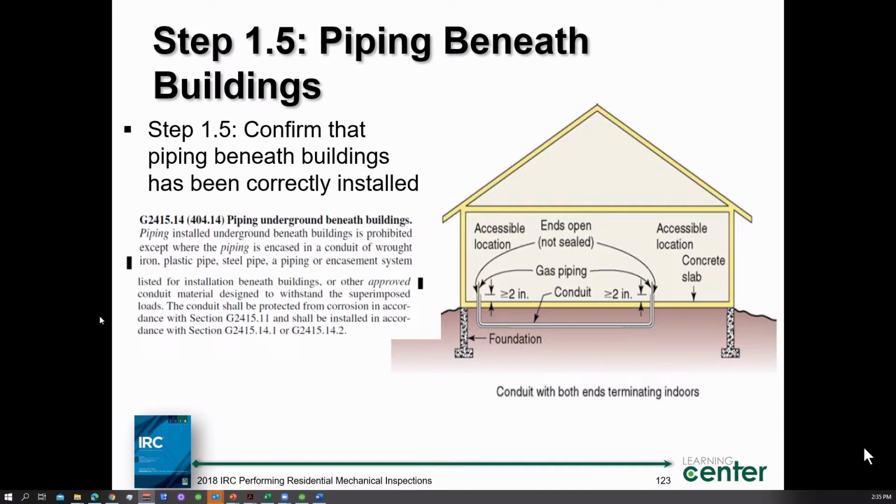But what happened to the vent of that conduit? The vent of the conduit. It's not needed in this case here. Vents on each end? Pardon me? Well, at some point there was a T coming into this conduit, and the older codes at least had to have it vented into the exterior. So if it did leak into the conduit, you would seal it on the end, and it would vent to the exterior.